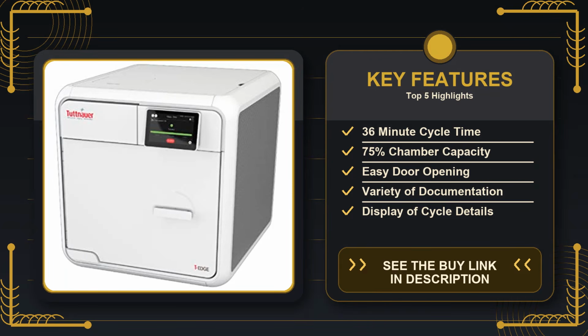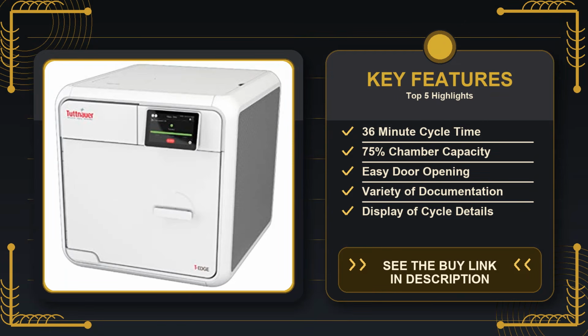Strengths become clear when you compare the EDGE10S to those cheap alternatives that often skimp on things like door swing and load ease. The door opens to a generous 110 degrees, which means you can slide trays in and out without wrestling them around a tight hinge. In a busy clinic, that small ergonomic win translates into less strain on staff and fewer dropped trays. The machine also includes multiple documentation options, barcode generation, printable records, and built-in software for tracking each sterilization event. If you've ever needed to prove that a specific set of instruments was sterilized on a particular date, these tools save you a lot of paperwork and audit headaches.